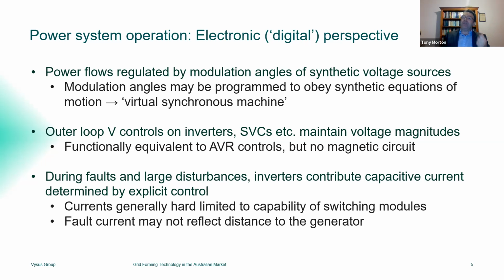So we've actually got a very different picture now of what the fault currents in the network look like. And it also means that we can't necessarily rely on those fault currents as directly as a measure of system strength, because they're not reflecting the passive characteristics of the network anymore.